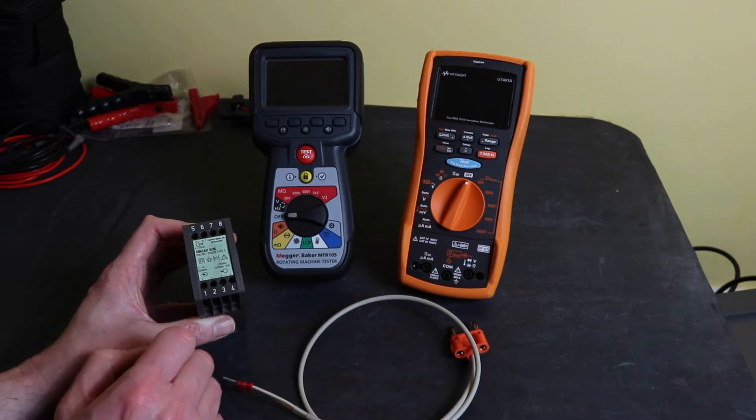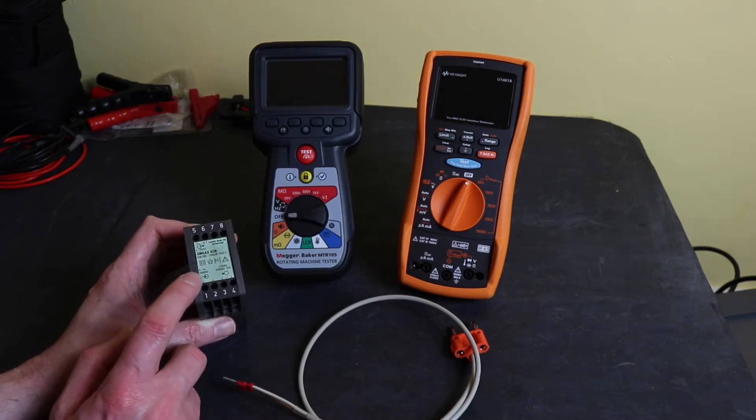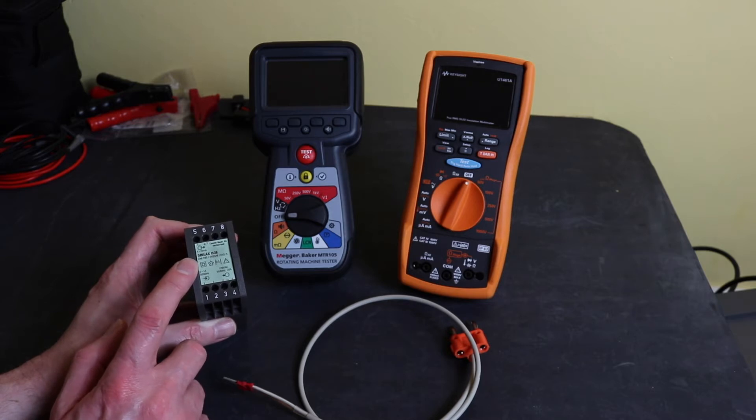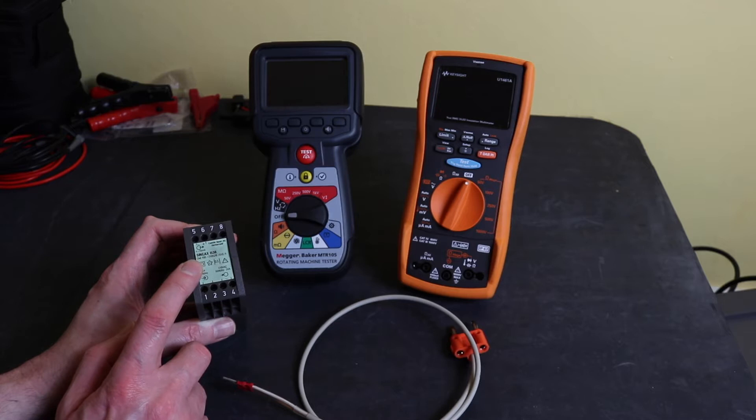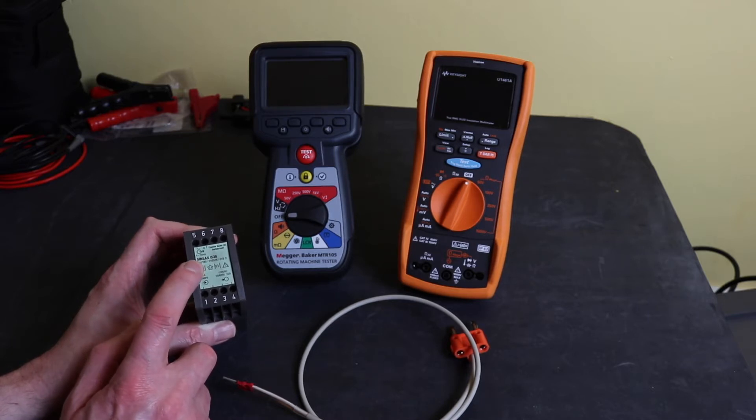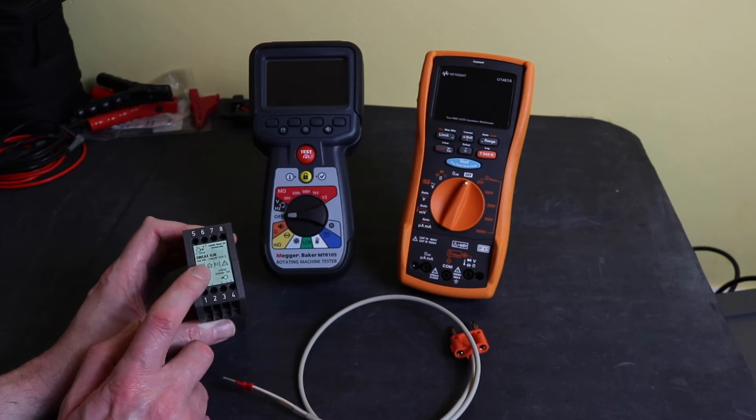And then in the control system for the settings you would reset that ratio back to the current transformer ratio. So the display on the control system would go between 0 and 2000 amps with the 0 being 4 milliamps and 2000 amps being 20 milliamps.